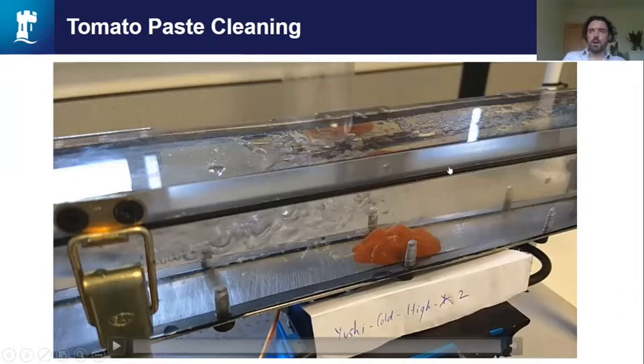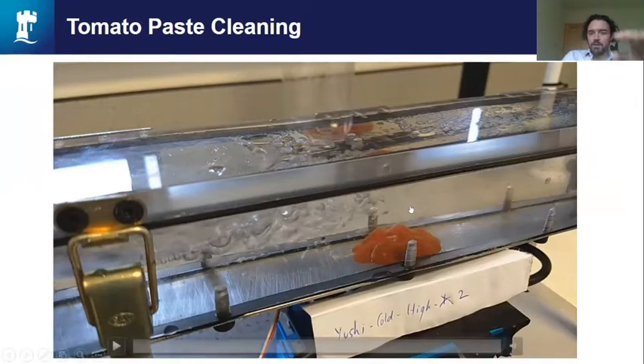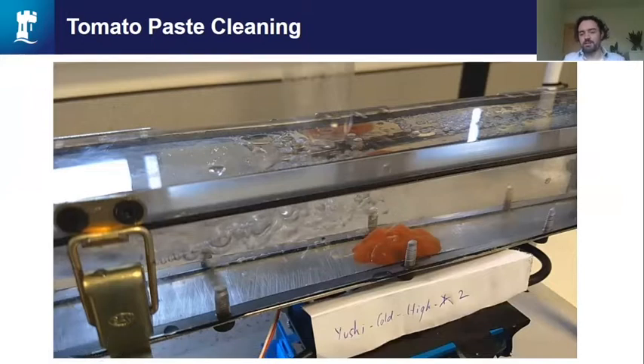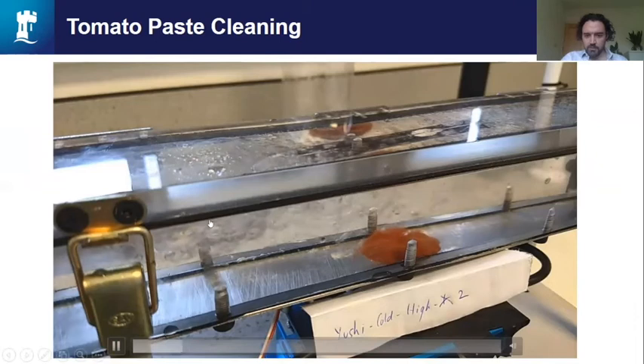The reason we need the camera goes back to something I was saying earlier: because we're using supervised machine learning, to train the model we need to know when it was clean and when it was dirty. For every ultrasonic wave, we need to label that clean or dirty. And how we do that is with a camera. Now, the clever ones will ask, why do you need this ultrasound sensor? Just use a camera. Well, the reason is because unfortunately not all food factories use clear perspex pipes. And once we've developed this model, we've now got some new ideas of how we can actually apply that model in an industrial setting.